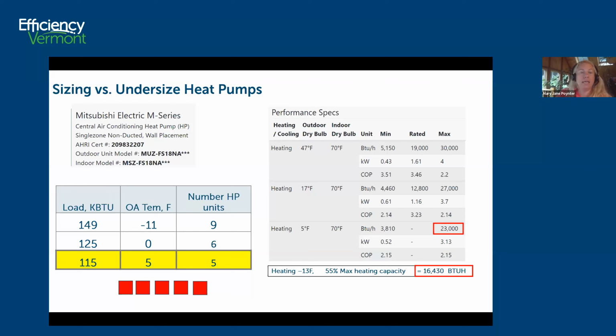But let's say instead of designing to meet the peak load at -11, you're designing only for 0. Well, now you only need 125,000 BTUs an hour, and you could go down to 6 units. But what if you were to size only for 115? Now, all of a sudden, you only need 5 units. So going from 9 units to 5 units is significant. And that just has to do with undersizing.